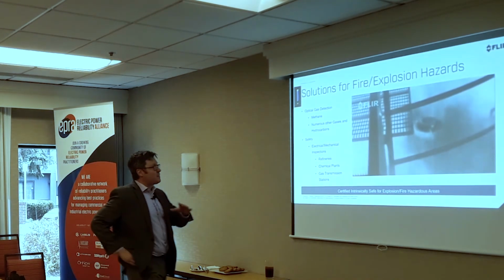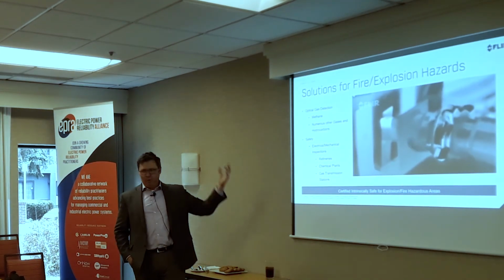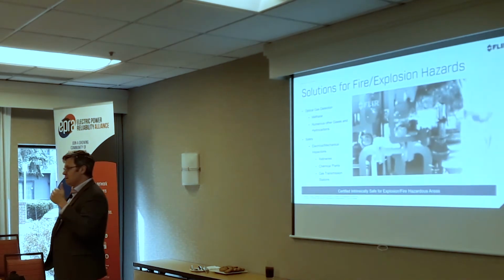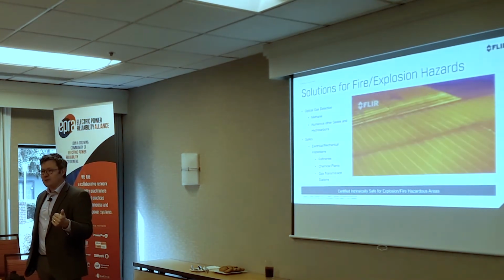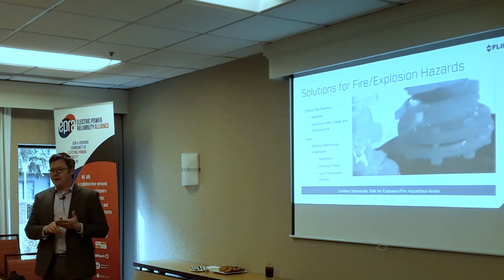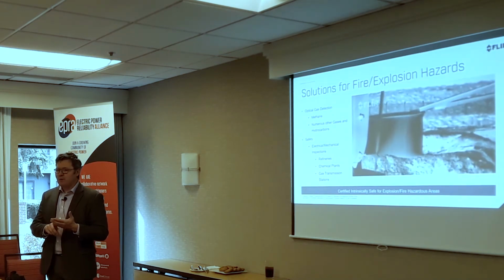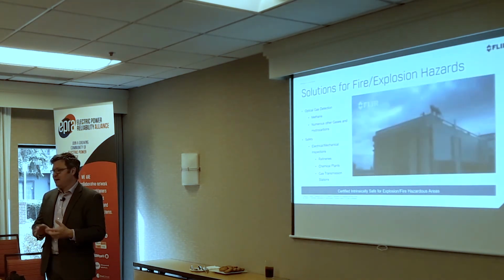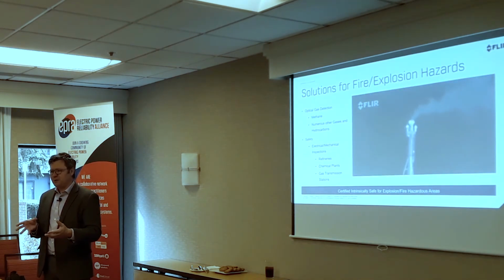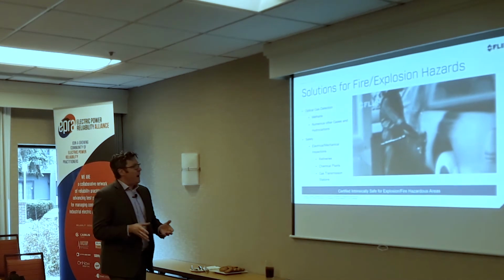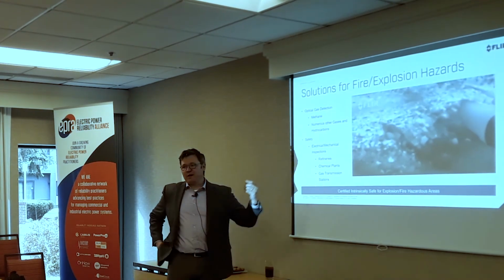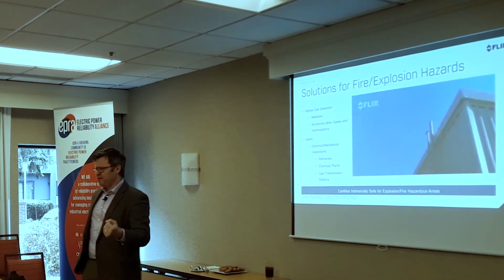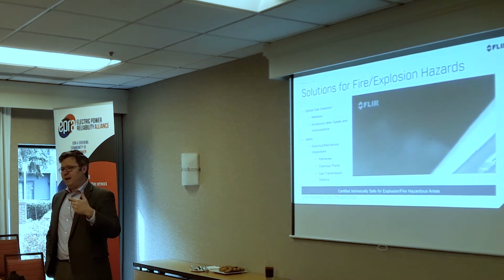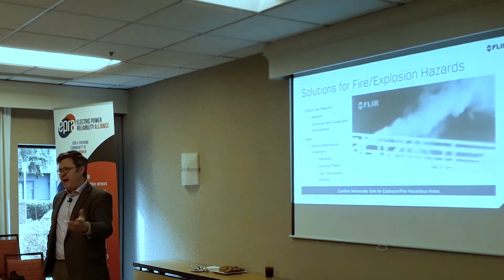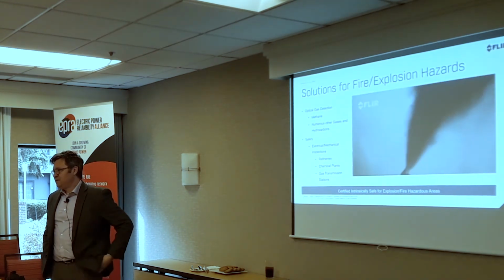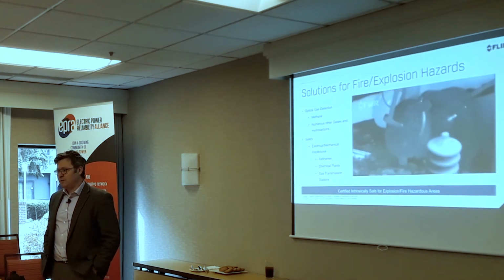I mentioned the gas imaging, and I'll point it up in this crowd, even though we are ostensibly talking about electrical maintenance today. This is related in one way because there are cameras that will image SF6 gas. That's your insulating medium in high voltage switchgear and some other equipment as well. But this is also representative of that intrinsically safe camera, which is designed to identify methane and a number of other hydrocarbons. And we advertise over 400 various invisible gases can be detected with this technology as well.